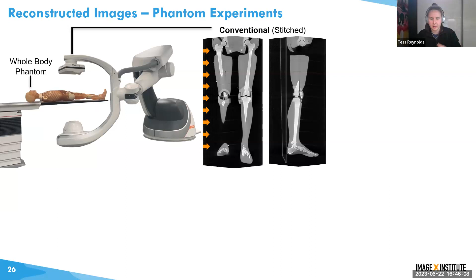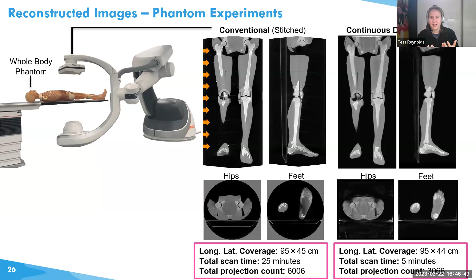If we then compare to our continuous dual isocenter, you can see that we're pulling back all of that detail. We can nicely see all those bones within this phantom. There's a slight drop of image quality at the hips in that top axial plane. But if we compare our lateral coverage, we've got the same. We're almost getting 1 meter and we're about 45 centimeters wide. And we've dropped that scan time down to 5 minutes, which is still quite long considering all our slow constraints on the rotation. But we've also halved that imaging dose, so there's still plenty of scope to push that imaging dose down further. But we've got these really nice images, and so we've got our entire area that we want to see in this single image that we can start using.